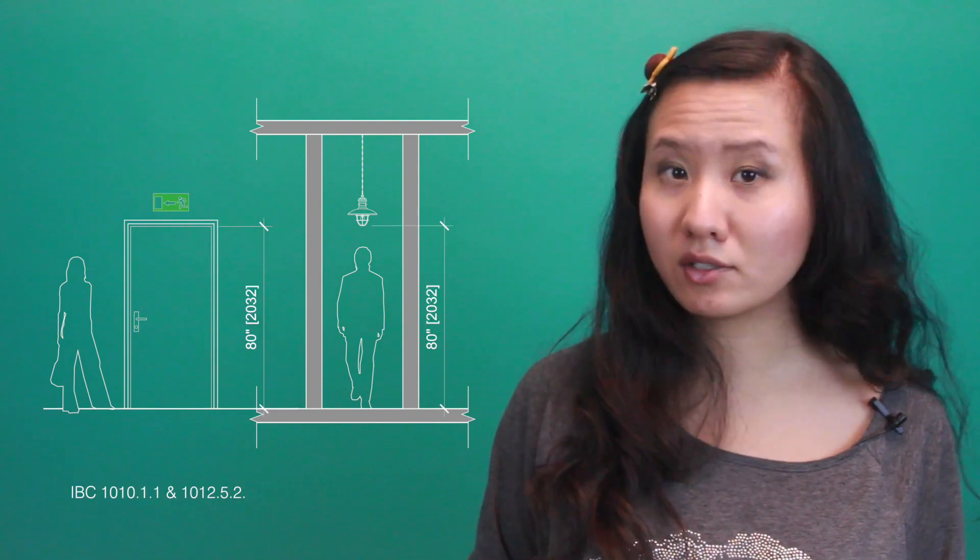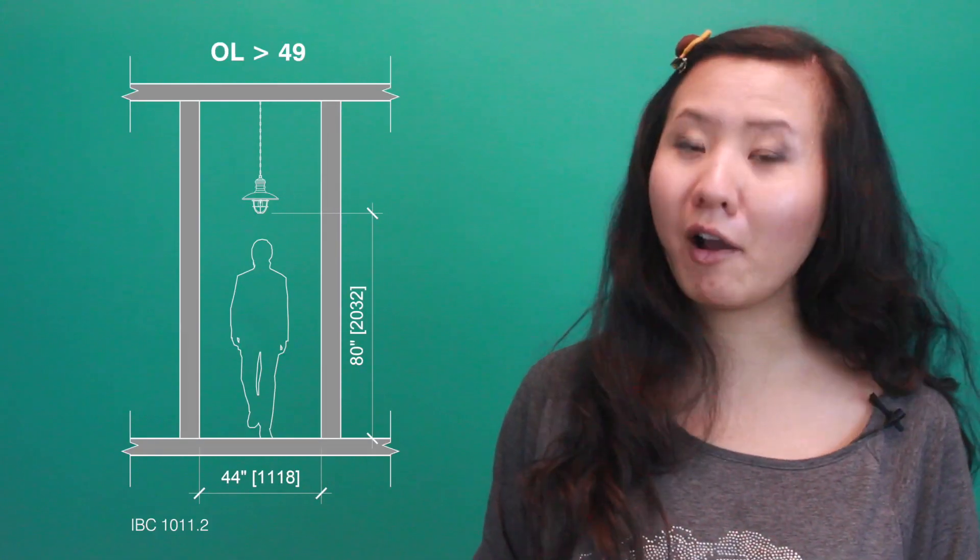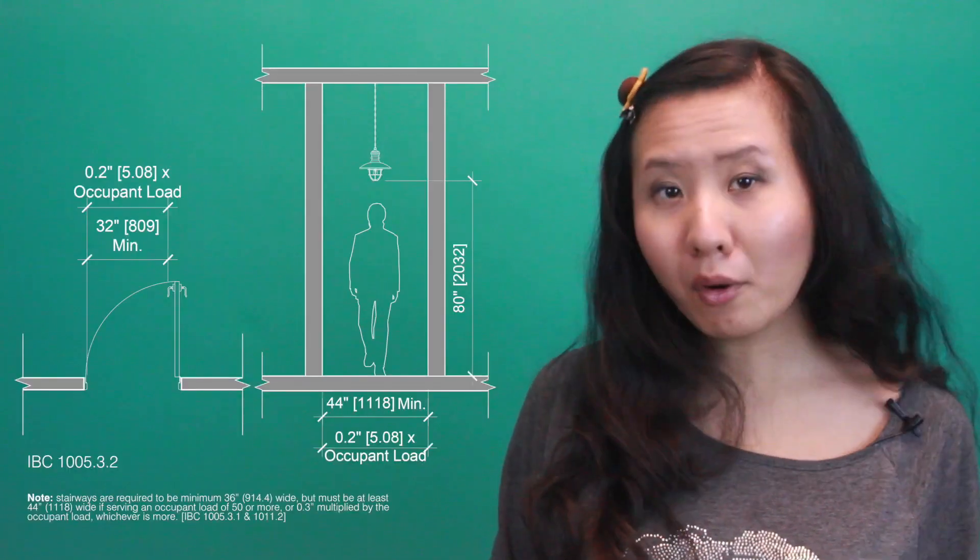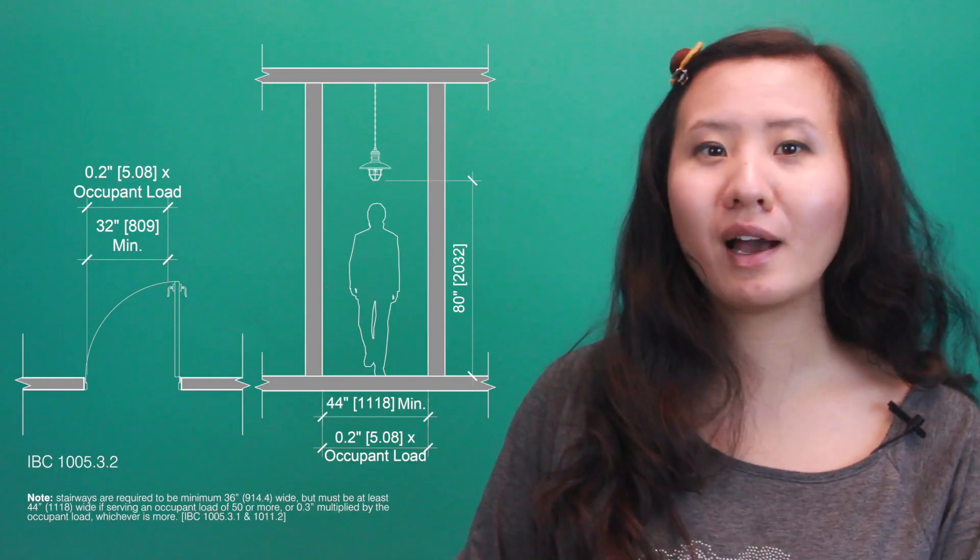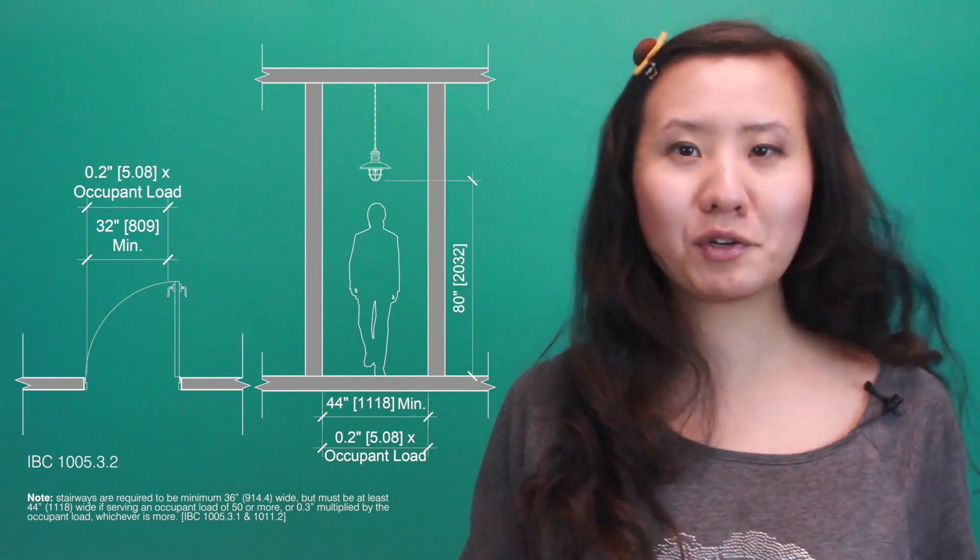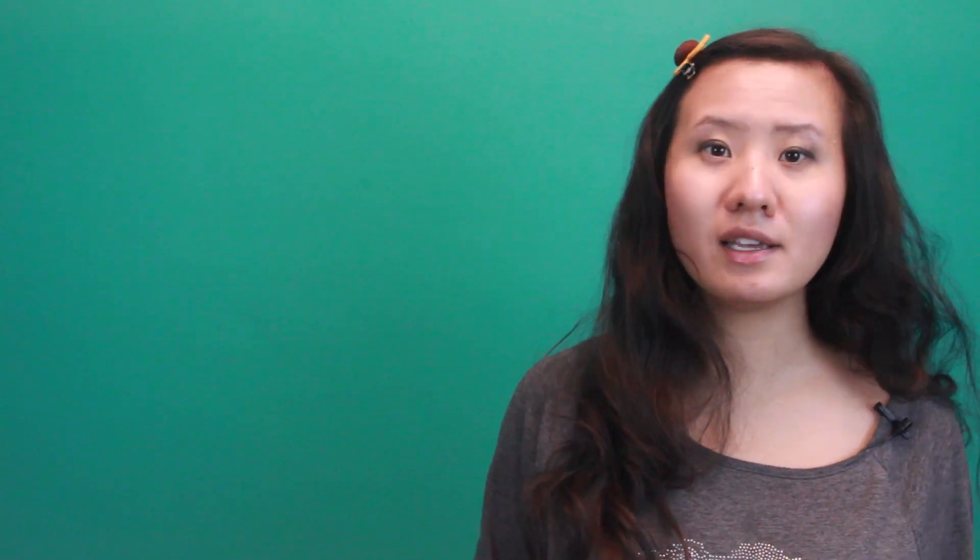The means of egress also have to be large enough to handle the occupant load. For example, doorways and corridors along a means of egress must have a clear headroom of 80 inches high, have a minimum clear width of 32 inches for doors, 36 inches for corridors, 44 inches for corridors serving an occupant load of 50 or more, or 0.2 inches multiplied by the occupant load, whichever is more. These width capacities may be reduced in certain occupancies if the space is equipped with an automatic sprinkler system.